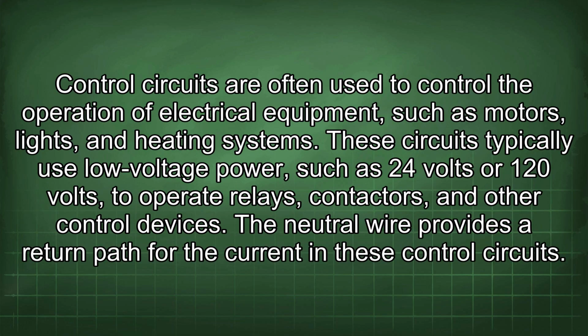Control circuits are often used to control the operation of electrical equipment, such as motors, lights, and heating systems. These circuits typically use low voltage power, such as 24 volts or 120 volts, to operate relays, contactors, and other control devices.